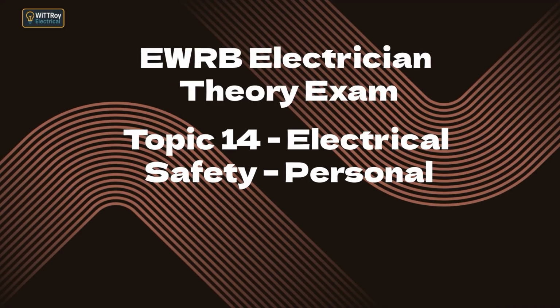14.2d Explain methods used to isolate and lock off equipment. Locking off means physically securing an isolator in the off position using a lock or device so it cannot be operated. A personal lock and tag must be applied, and only the person who installed the lock may remove it. Lock-off prevents accidental or unauthorized re-energization.